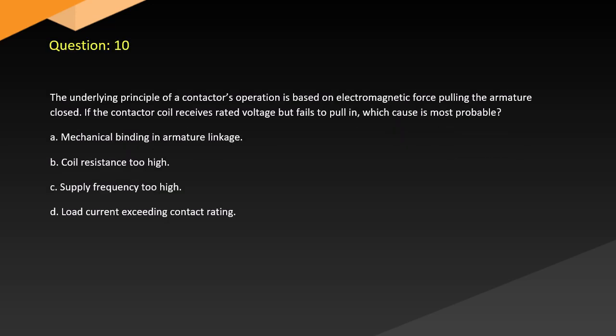Question 10. The underlying principle of a contactor's operation is based on electromagnetic force pulling the armature closed. If the contactor coil receives rated voltage but fails to pull in, which cause is most probable? A. Mechanical binding in the armature linkage. B. Coil resistance too high. C. Supply frequency too high. D. Load current exceeding contact rating.